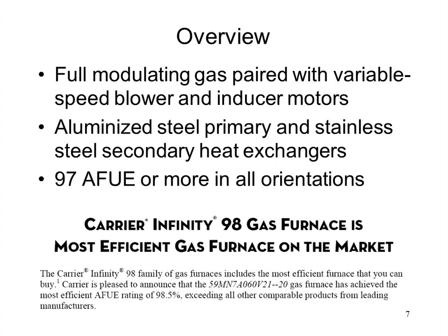As you probably know, this furnace, along with all of the other furnaces in the condensing furnace lines from Carrier and Bryant, can be installed in any orientation. There are no dedicated models that require you to have a certain model number to be able to put it, say, downflow or horizontal or something like that. Every single model is fully multi-poise, which means we can rotate it in any direction. There's a few things we'll have to do to modify the unit, and I'll show you those in a second, but they are very easy and take less than 5 minutes.